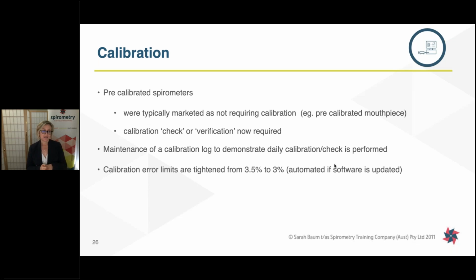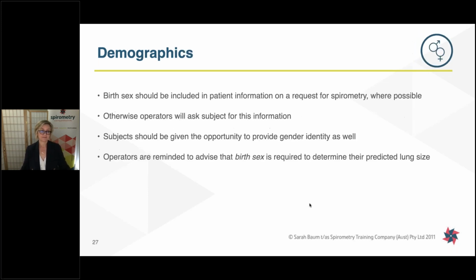It's also been recommended that we maintain a calibration log to demonstrate that the daily calibrations are actually being performed. And the calibration error limits have been tightened, and you might not notice this, but currently it's a 3.5% error limit on a calibration. That's just been tightened to 3%. This will be something that automatically happens in the background if you update your software, or if you have a newer spirometer, it's possibly already there in the settings.